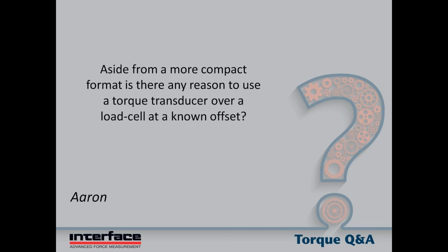Yeah, good point, Chris. To expand on that a little further, as with force measurement, the idea is to get the measurement basically as close to what you're trying to measure as possible. So on a load cell system, if you have a bearing or a pivot, you wouldn't want to measure through the pivot, for example. Same thing with torque. The inline sensor can get the torque sensor right as close as possible to what you're trying to measure. If you scheme up some system where you react the load using load cells, you may end up having the load cell quite a bit removed through a number of joints and pieces away from what you're trying to measure. So all of those have effect and influence on the measurement. As close as you can get the sensor to what you're trying to measure usually is the better.